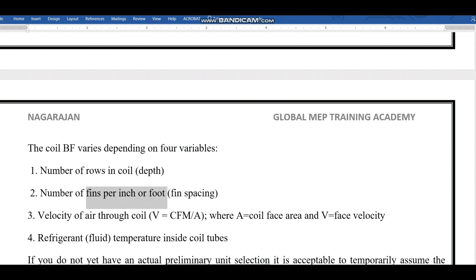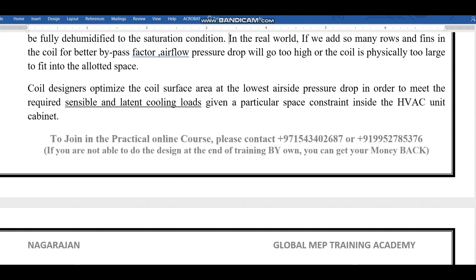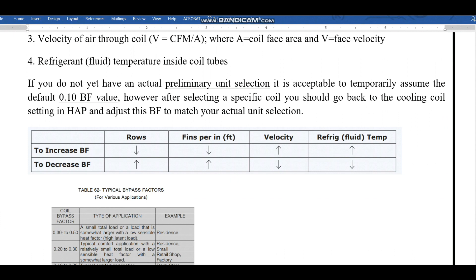A few main factors which affect the bypass factor: first, the number of rows in a coil; number of fins per inch, the fin spacing; velocity of air through the coil. Normally in the drawing they will mention like the face velocity in the coil should not exceed 2.5 meters per second. Finally, the refrigerant temperature inside the coil. Coil designers optimize the coil surface area at the lowest air side pressure drop in order to meet the required sensible and latent cooling load given a particular space constraint inside the HVAC unit cabinet.